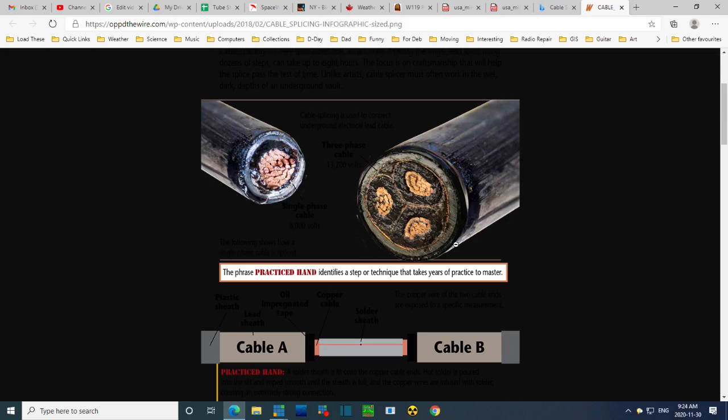That's just showing a 3-conductor cable sliced right through, so you can see the 3 conductors. You can see the copper shield. This shield I'm outlining was an idea somebody got, named Hochstadter, and so he invented the Type H cable. Before that, there was no shield here. So the electric lines of force pressured the paper all the way from the conductor edge out to the underneath of the lead sheath. You can really see now there's a lead pipe here, right? The result of that is lateral voltage gradients over surfaces of paper.